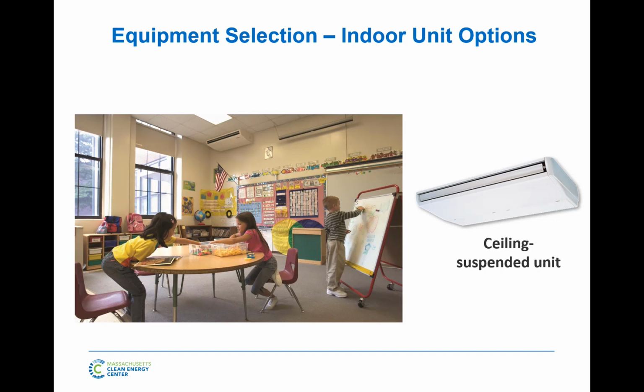The windows are where you mostly have your heating and cooling load. So we're throwing air all down along those windows for an entire classroom. And the benefit here is the unit's up off the ground, and no one can touch it. So I like calling them classroom units because, one, usually it's a retrofit application, so you can install this without tearing into the ceiling, tearing into anything below the building or on the side. And then when all these kids come in, throw their backpacks somewhere, throw books somewhere, throw crayons somewhere, it's not going into something like a floor console unit. It's up out of the way and can't be touched, which is the safest place for an HVAC unit.